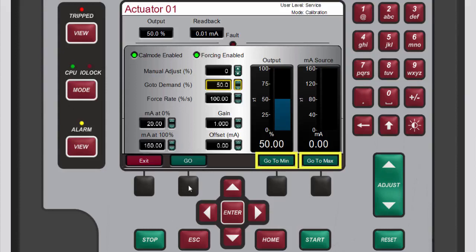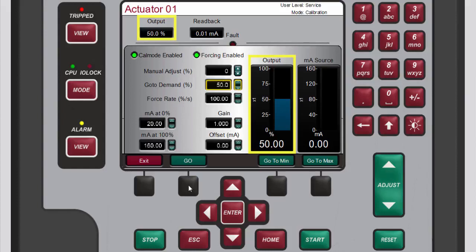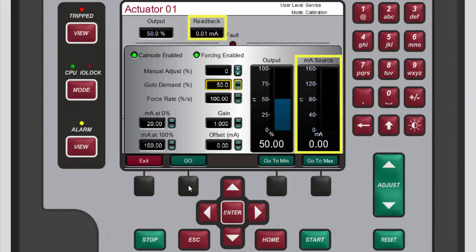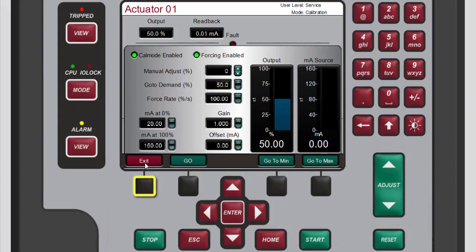You can also change the values in the gain and offset boxes to calibrate the signal. For a properly wired and functioning circuit, the output gauge and output box should match — output is the value the software is requesting. The milliamp source gauge and the readback box should also match — milliamp source is the value measured at the positive terminal for the channel and readback is the value measured at the negative terminal. When you are done forcing outputs, press the black function key below exit.